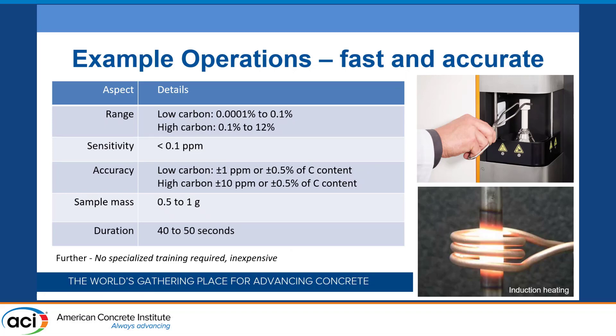A technique like this takes carbon contents or sulfur contents from very low abundances up to 12%. We're talking about detection to the fourth decimal place of carbon — sensitive to 0.1 ppm of the element within the sample. You get pretty accurate and consistent results across different amounts of carbon. The sample mass is pretty small — only half a gram or a gram — which goes into this crucible. You're measuring it in advance, then putting it in the induction furnace. This is just an example of induction heating: you have highly localized high heat.